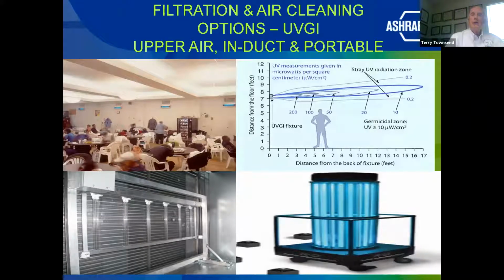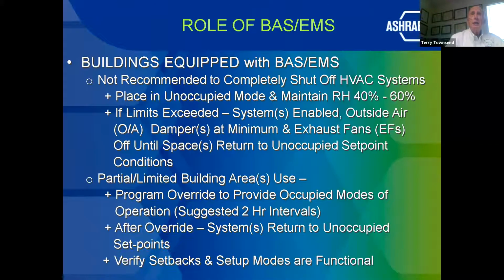Now, the lower left hand is UVC in-duct, and then you have the UVGI portable filtration that is available for application. So now we look at the building automation system. And let me hurry on here. It's not recommended to completely shut off any of the HVAC systems, even if you place it in unoccupied mode. Maintain the relative humidity between 40 and 60%. If the limits are exceeded, then the systems are enabled.